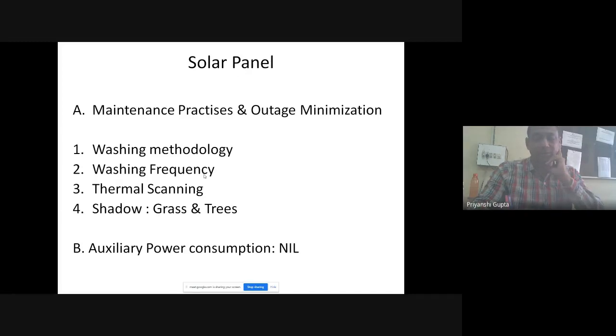There is a thumb rule for hot spots: keep the temperature more than 5 degrees above the local temperature. For example, if the ambient or average panel temperature is around 35 to 40, and a particular area shows 50 to 55, this is a hot spot. This hot spot signifies deterioration of the panel.